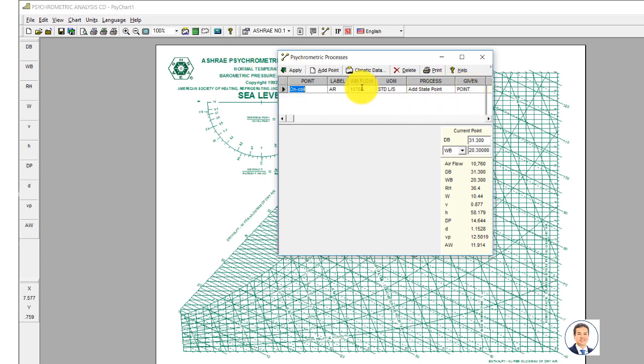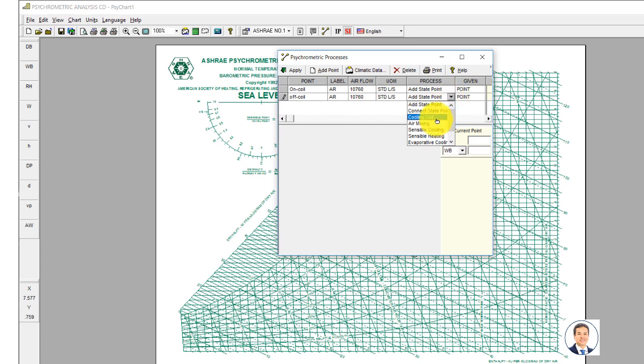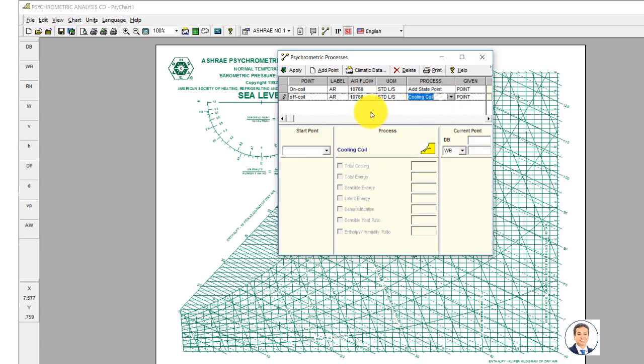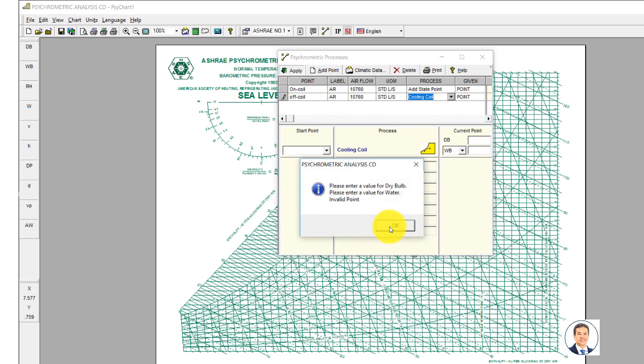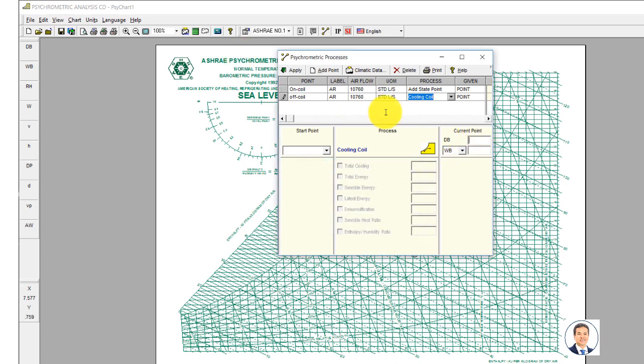And then add a point again. We have the off-coil condition. Off-coil, same process for our value. So let's connect these. Let's create the cooling coil, air handling unit process. Apply, by the way. Oops, please enter the dry bulb. We didn't input it. The off-coil is 10.8 dry bulb, and the wet bulb is 10.7. We could also use the relative humidity given earlier, which was 98.4. So 10.7. Let me put the relative humidity instead for variety. So we have 98.4, the given value. So here's the capacity, right? Apply. This is our process.